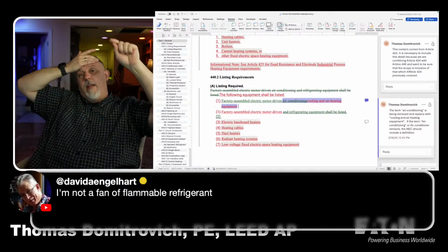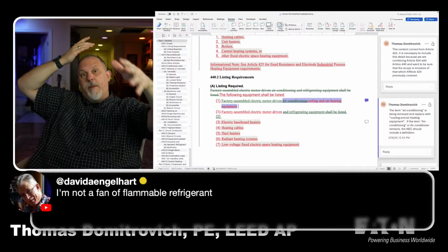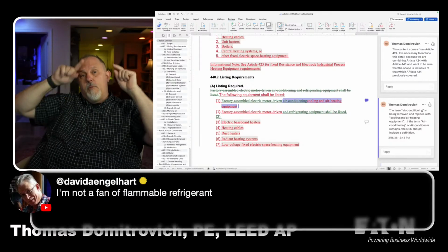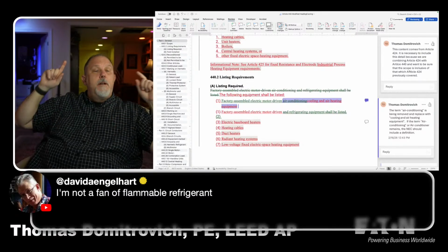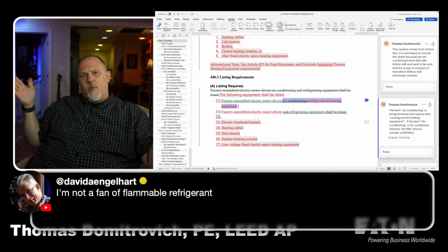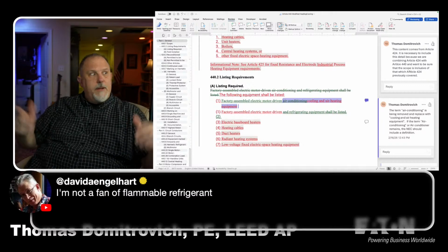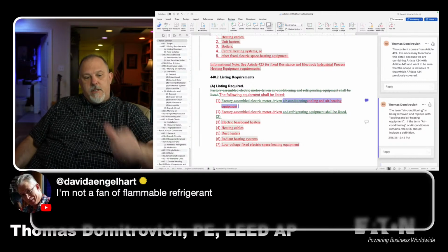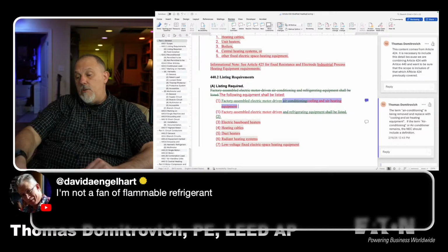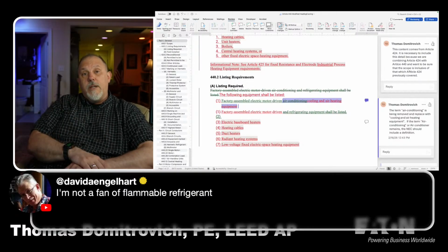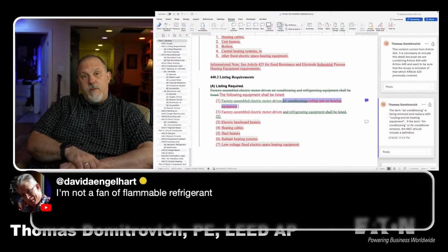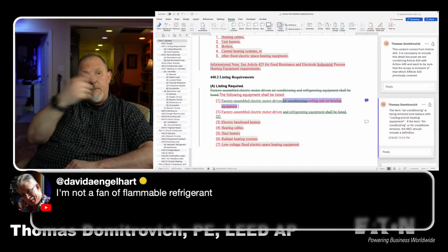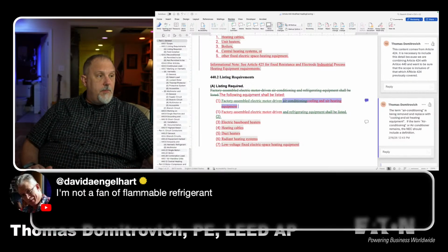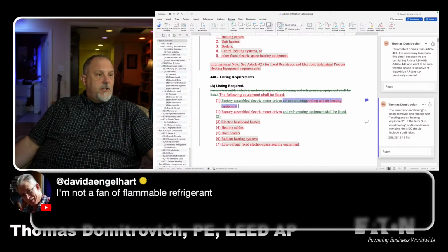I put a public input in that would require a battery backup for HVAC or heating and cooling equipment that includes that flammable refrigerant that would last, I think I said 2 hours or 1 hour or something like that. They can argue about that because of the flammability of it, because it's being used in panel 2 to argue against GFCIs. And if it is that hazardous, then I think that warrants something in 440. So I put a public input in for that. But I'm going to describe that.